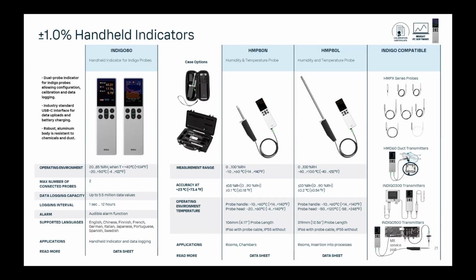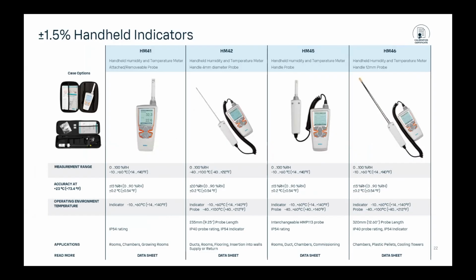If you weren't looking for something so robust and technologically advanced as the Indigo 80, we also have the HM40 series. I figured I'd highlight this because I believe there's going to be a raffle at the end for one of these. So a little detail about these. These are still high-end accuracy, plus or minus 1.5%. The indicator stays the same through all the probe options. However, it's a little bit stripped down. You don't get the same data logging, you don't get the dual probe support, but it is a great portable reference. It comes with that traceable calibration certificate. So if you ever are doing any adjustments or calibrations yourself, this is a great option for a reference meter to use.